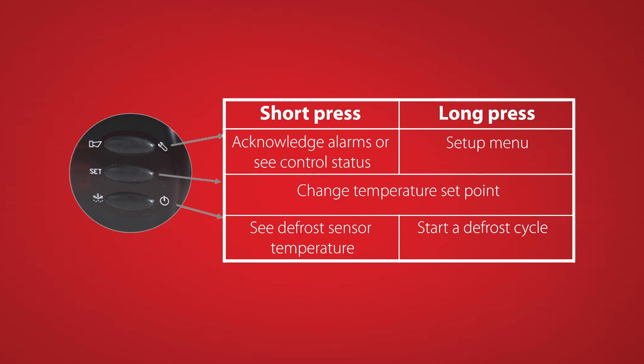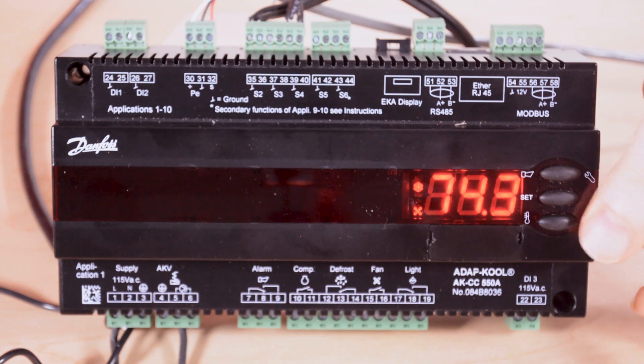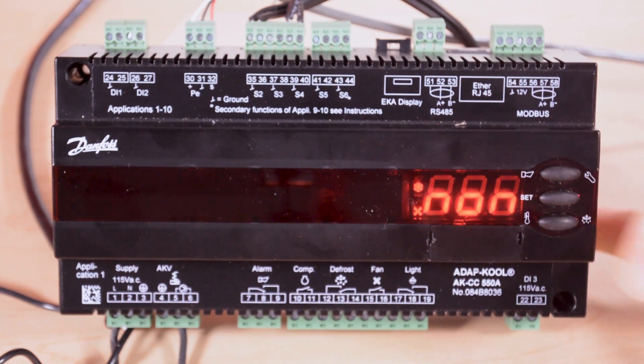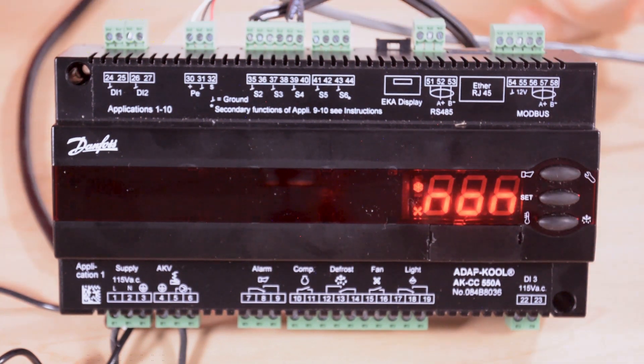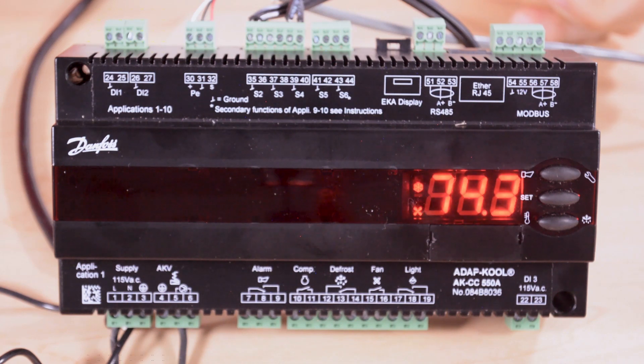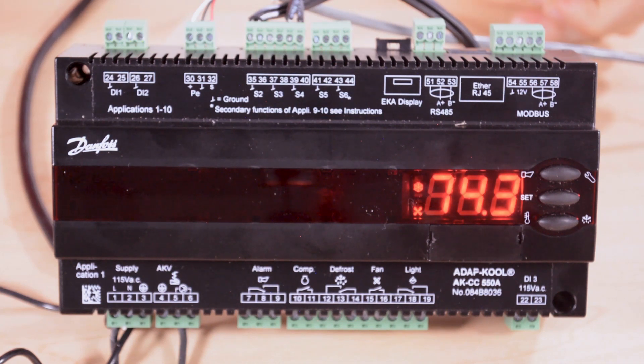The bottom button is used for scrolling through parameters when we're not in the parameter listing. We can use it to look up the defrost termination temperature, and if there's no temperature sensor assigned it'll just read NON indicating that there is no defrost termination sensor set up in this controller.